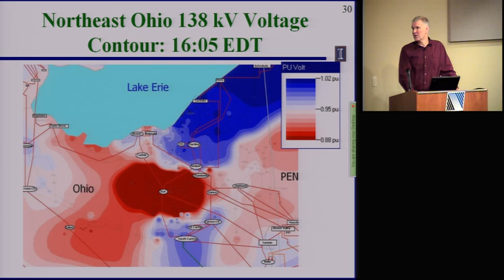Eventually they sag into something. There were actually zone 3 relays, which are talked about in the report, that were starting to trip lines. So we started getting the classical cascade occurring, but it occurred over many minutes, on the order of about, let's say, 3:36 or 3:35 in the afternoon to about 4:10. So you had 35 minutes of action.